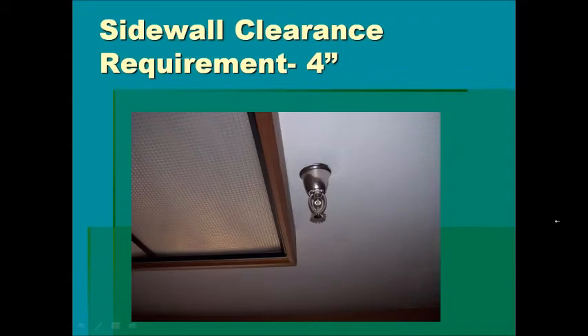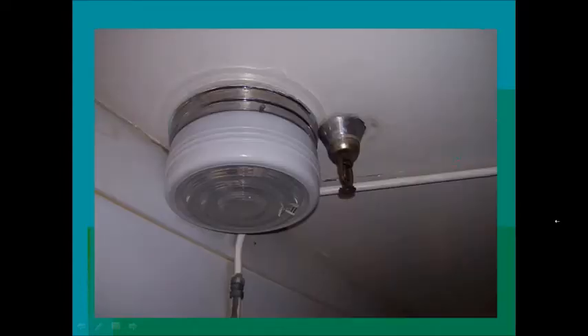I see everything from sprinkler heads completely covered and compromised to storage height exceeding that 18 inches. We see sidewall clearance problems. You need to provide at least 4 inches of sidewall clearance around a sprinkler head from any kind of fixed appliance or fixture that's on a ceiling or a side wall or a column. You know, that light wasn't there originally, but somebody had a need, and they never considered how that sprinkler head is now compromised by the presence of that light fixture.